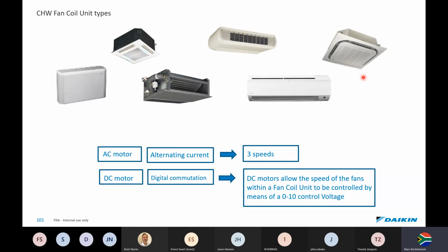So now that we've looked at the chillers we offer, Daikin also offer a range of chilled water fan coil units. There are two types. We offer AC motor, which is alternating current, for the simple orthodox 3-speed. We also offer digitally commutated motors. So we normally control these with a 0 to 10 control voltage, multiple fan speeds, and very low energy consumption, and a lot quieter than the 3 set speeds, and also a lot lighter on electricity than the alternating current.